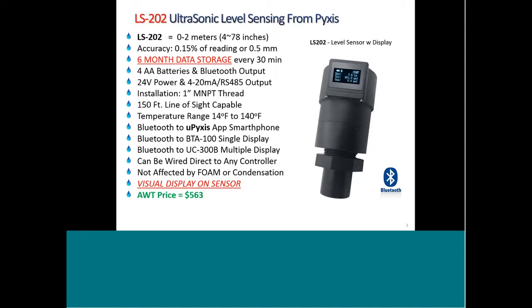The tank level monitor can be programmed for the timing of recording events, from continuous recording up to once per hour, and multiple steps in between. The default is once every 30 minutes, and at a 30-minute frequency of measurement, you will be able to run on 4 AA batteries for approximately 9 months. The device will store 6 months of inventory data at a frequency of measuring every 30 minutes.